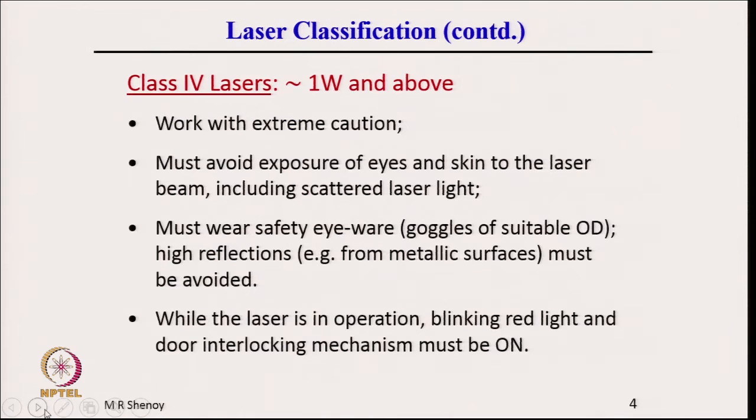Now, let us go to the next class, which is the class 4 laser. So, class 4 lasers have powers of the order of 1 watt and above. All lasers with power greater than or of the order of 1 watt, sometimes even 500 milliwatt, are classified as class 4 lasers.